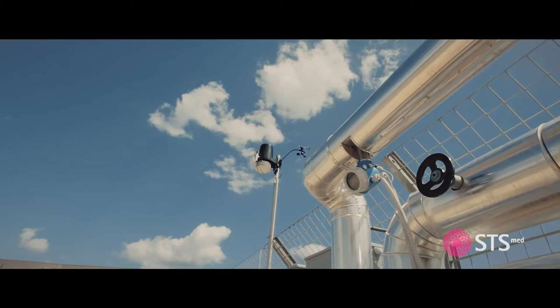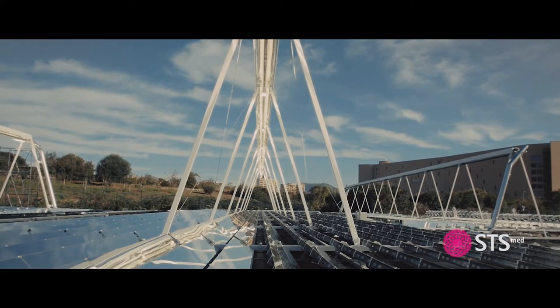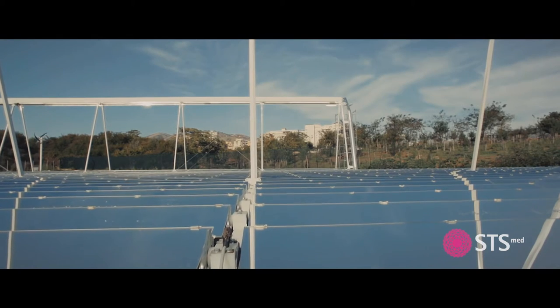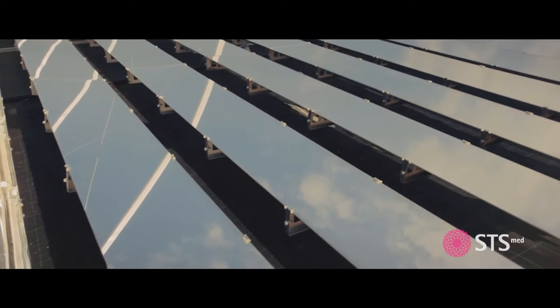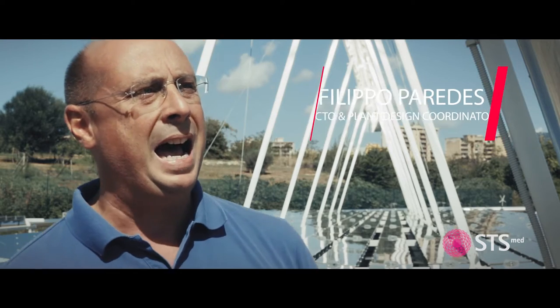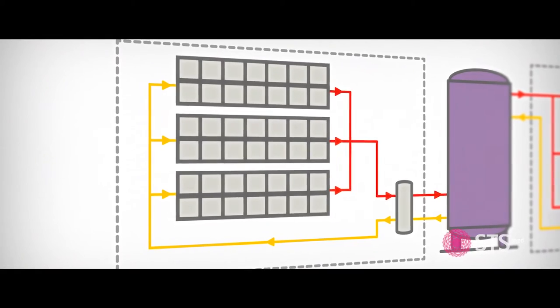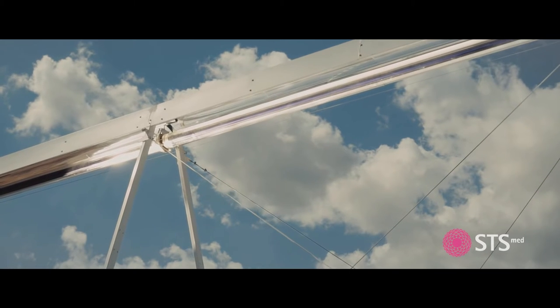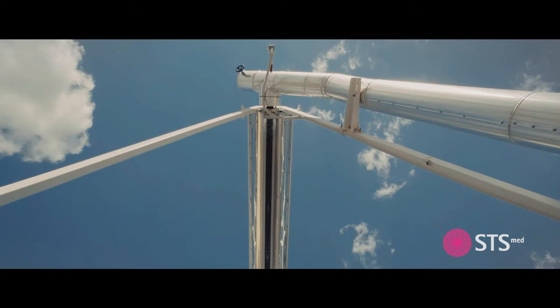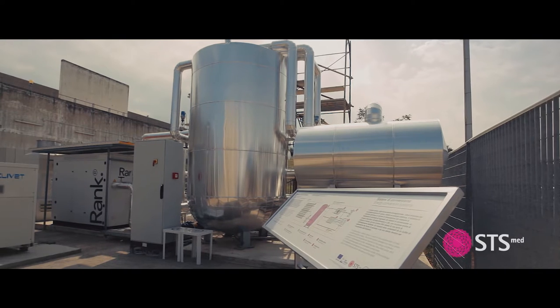I was in charge of the design, installation, and commissioning of the system installed here inside the University of Palermo campus. This is the first time in Sicily that we have created a solar laboratory available to all researchers at the university and to technicians who want to understand the use of solar systems. We have installed here three linear Fresnel collectors — mirrors able to heat a diathermic oil inside the absorber tubes. We heat the oil to about 250 degrees Celsius and store all this energy inside a thermal storage unit.